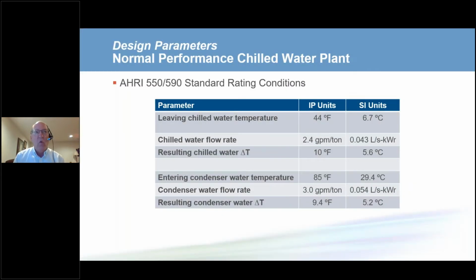A question is, how are many systems designed? Many systems are designed today and have been for many years using the AHRI standards. Those are how chillers are rated. And there are some base or standard conditions, and those are shown here on our screen, the leaving chilled water temperature. And the important parts are the temperature differences. On the chilled water side, it's about 5.6, between 5 and 6 degrees C. On the condenser water side, it used to be a higher number because chillers weren't as efficient, but as chillers became more efficient, the delta T came down to just over 5 degrees C.